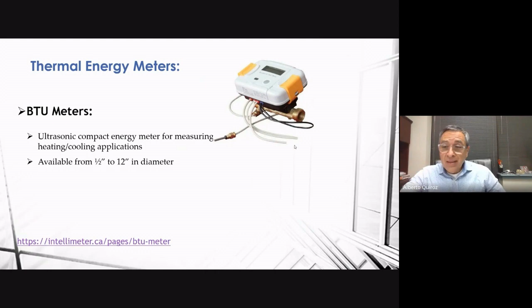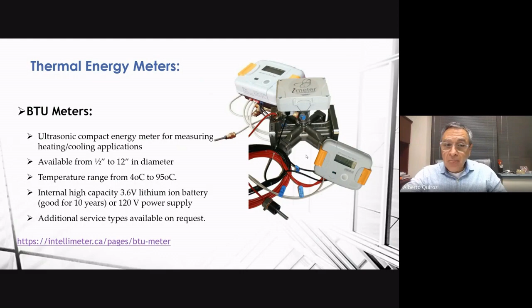On heat meters, you can ask Mark. We typically have stock, except for large orders or odd sizes. We have heat meters that speak Modbus or MBus, which come with pulse output as well, and you can order them with a power supply. Why? Because in these meters there's no mechanics, it's all electronics, so they come with a battery. If you're concerned about battery duration, order it with a power supply, and when integrated, it runs in the same wire as the communication, which extends the battery life.